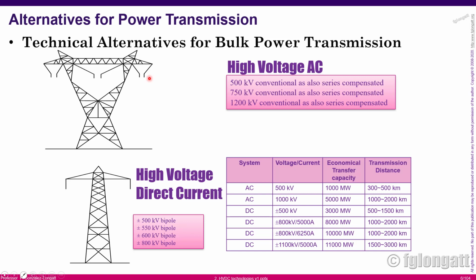In some countries, they almost reach 1,200 kV. Okay. However, one of the situations when you are using a very high voltage for transmission is that the transmission line in AC has a big capacitance, and this big capacitance makes voltage control a real problem. That is the reason it is quite typical that if we are working in extra high voltage or ultra high voltage, you will find many compensations. I mean, reactive power compensation, and that is one option.